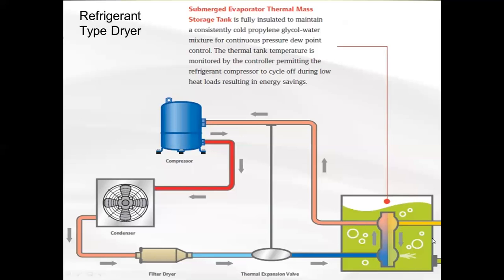Okay, the other side of the heat exchanger is a loop, and there's a little pump on the other side that we'll see on the next slide, and it just circulates this cold glycol to another heat exchanger that actually cools the air. So there's a little pump in here that's pumping back through this side of this heat exchanger, because this stuff is going to come back a little bit warmer, because it's the flow that has cooled the air down, and then it goes out here into the tank. And that's how this is getting cool. And then the pump pulls it and circulates that side of it.